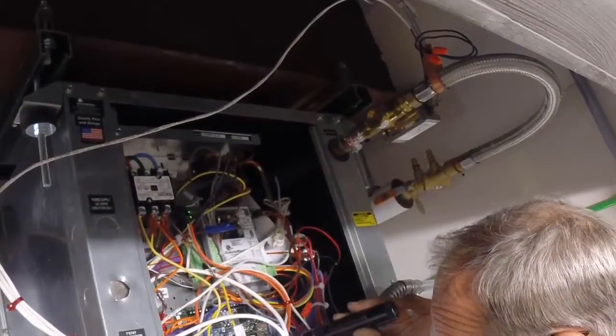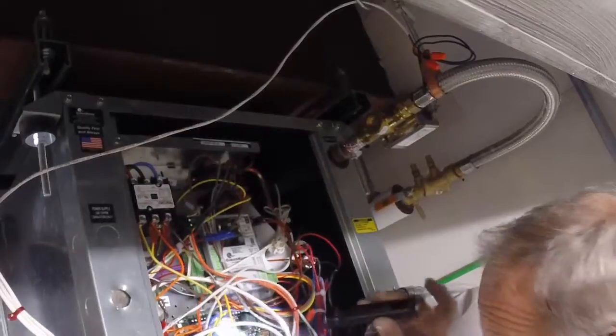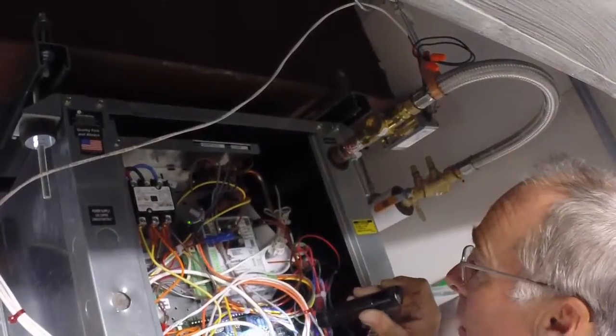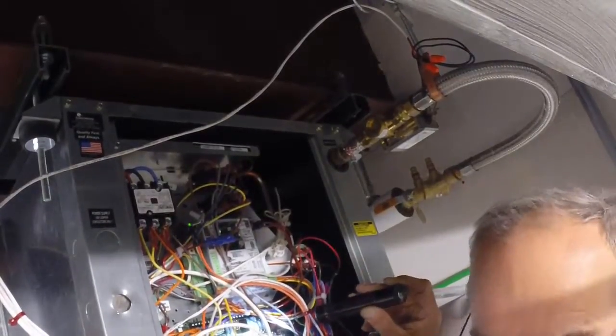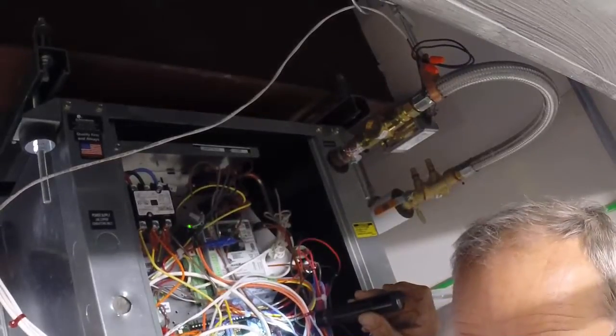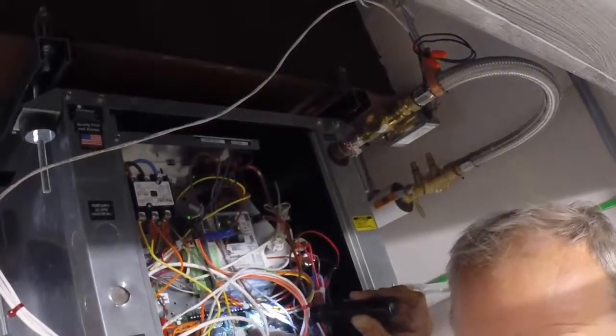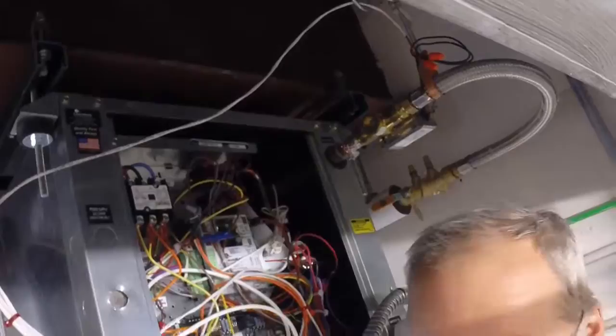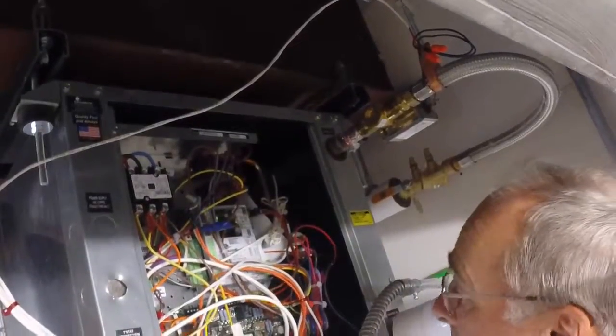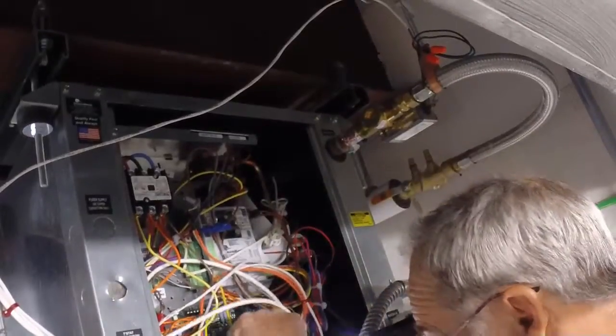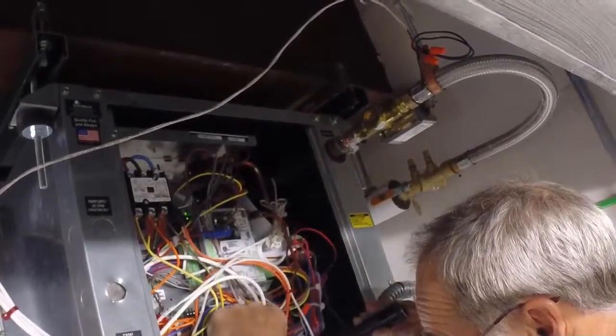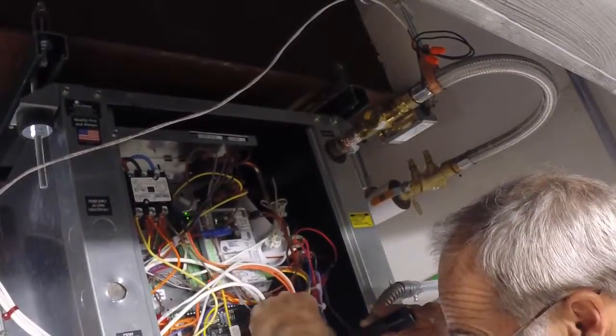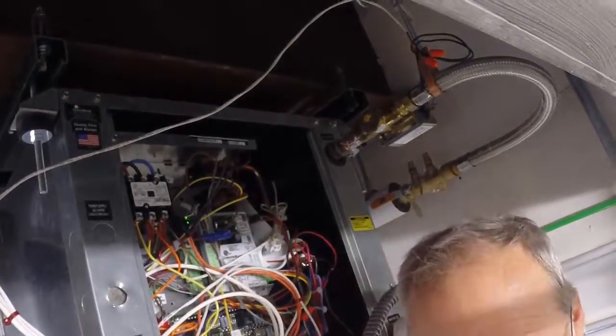So this is basically a thermostat now. You could actually hang a regular thermostat through these connections. A heat pump thermostat and hang it in the air and it would heat and cool. So it has a set of dip switches on it. One controls these auxiliary relays. And the other one, this dip switch six, is used to report alarms back to the main board. So if you ever have to change a DXM board, there's a couple of jumpers you have to make sure are cut on your units.